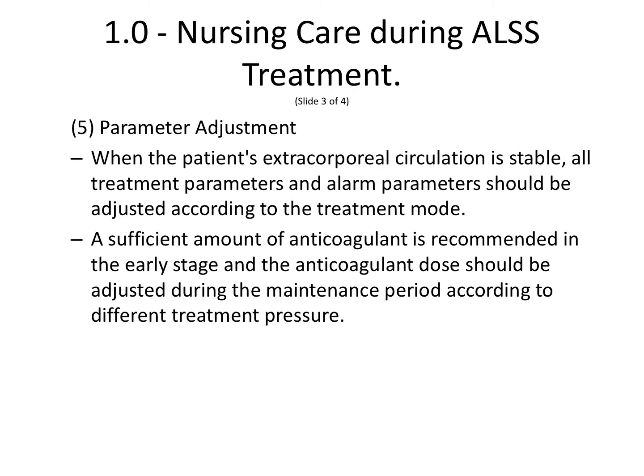5. Parameter adjustment. When the patient's extracorporeal circulation is stable, all treatment parameters and alarm parameters should be adjusted according to the treatment mode. A sufficient amount of anticoagulant is recommended in the early stage, and the anticoagulant dose should be adjusted during the maintenance period according to the different treatment pressure.